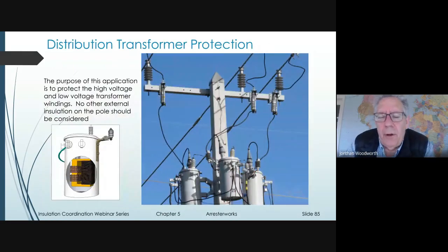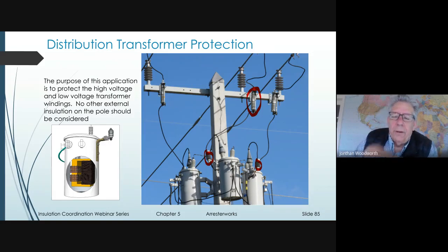This is a very common distribution system where we have a three-phase transformer, and we have arrestors that are protecting each phase. And then we have fuses that are providing overcurrent protection, but arrestors are meant for overvoltage protection only.